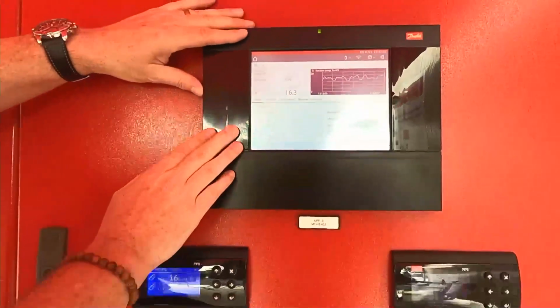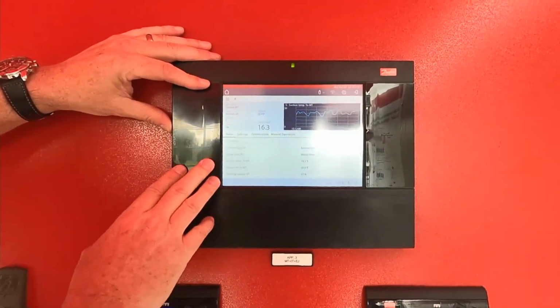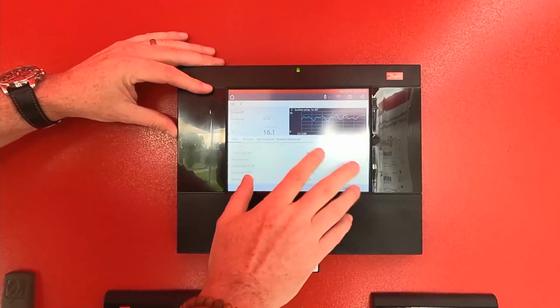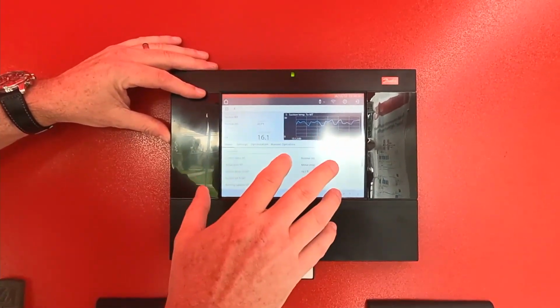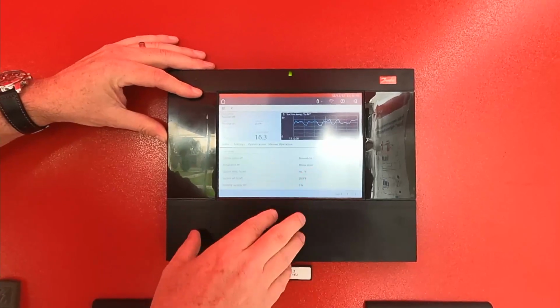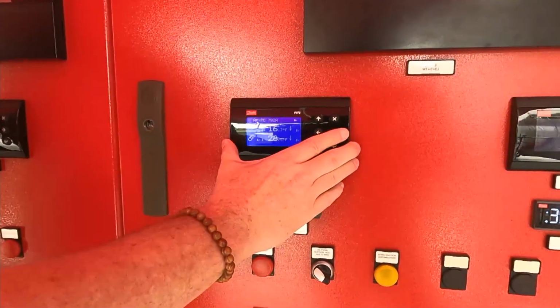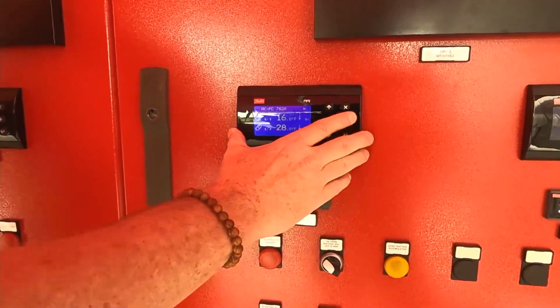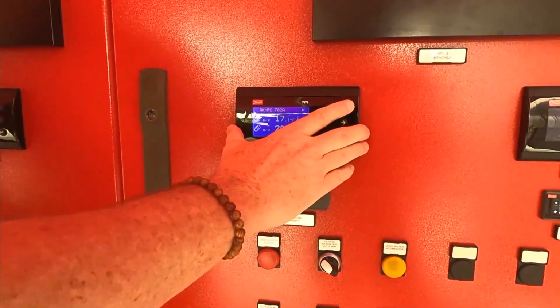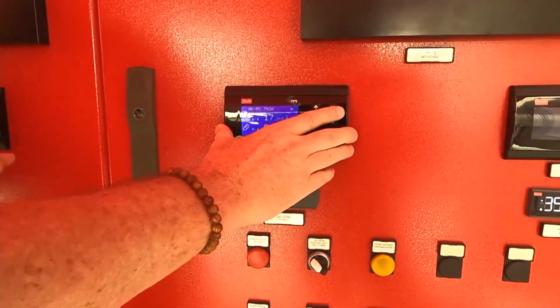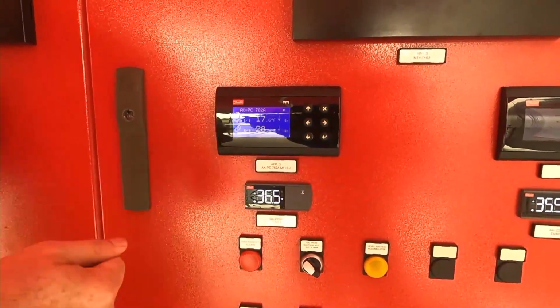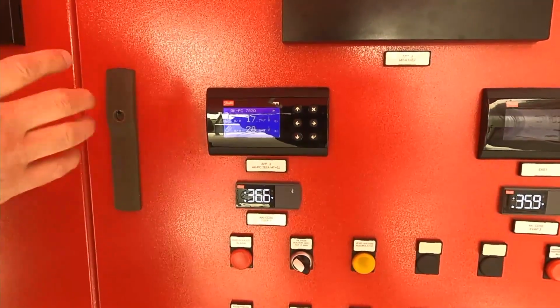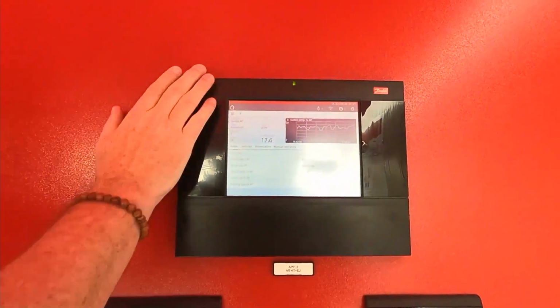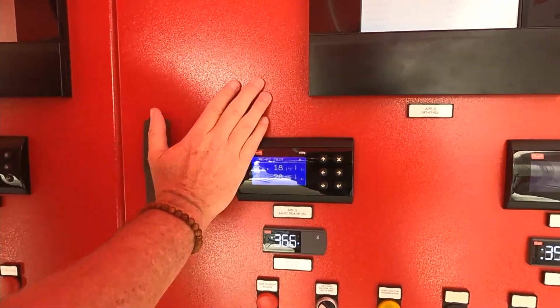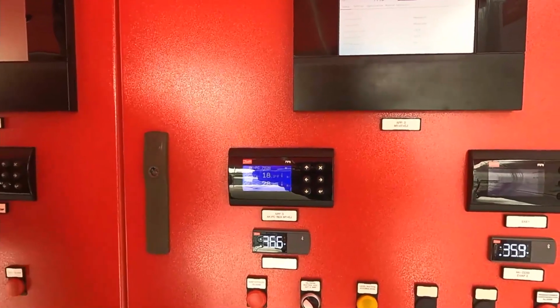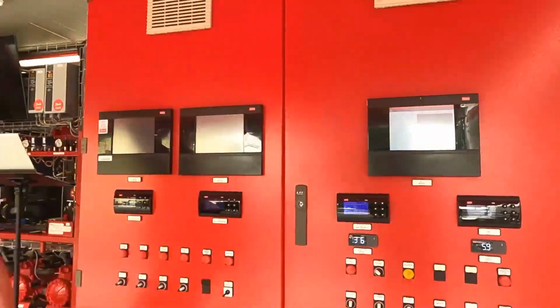The system manager isn't meant for setup and configuration. It's meant for visibility and remote access to the pack controller. So you can't do anything with inputs and outputs here other than override some functions like compressors and fans and valve percentages. If you use our MMI remote display, it gives you full access to the pack controller, but it's a small display. It takes some getting used to. And then we have a software called Service Tool where you connect directly to the pack controller. So the interaction and the ability to make changes really is kind of good, better, best, with SM800A being good, this being better than the accessibility this will give you, and then the best would be our Service Tool software. I hope that answered the question.